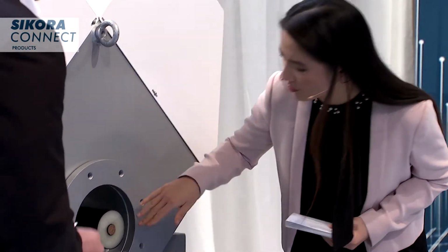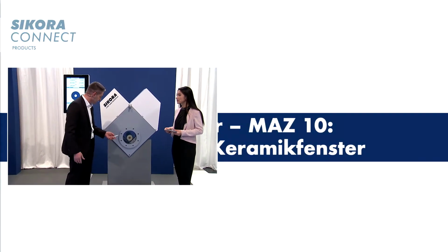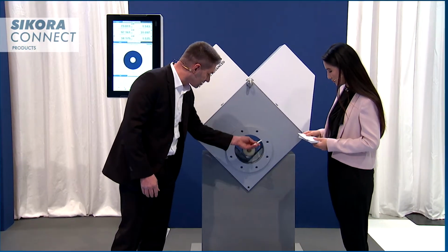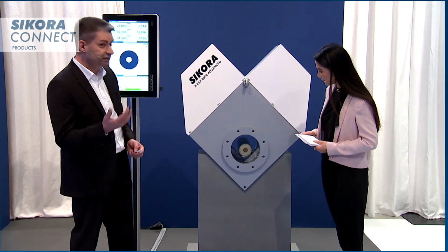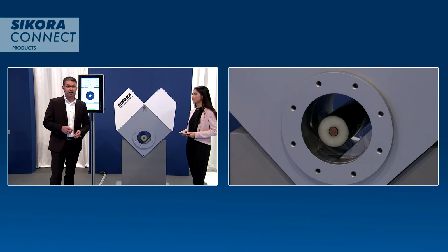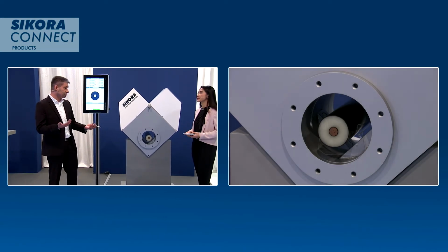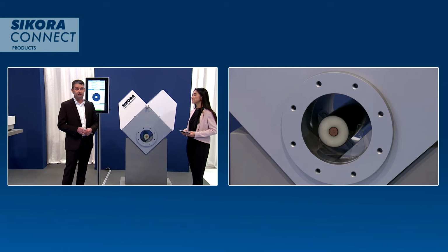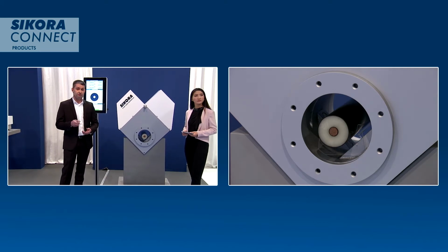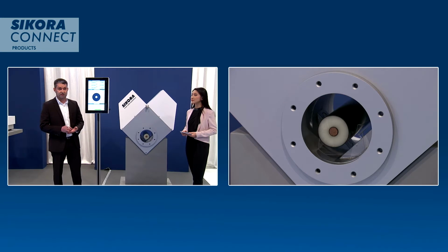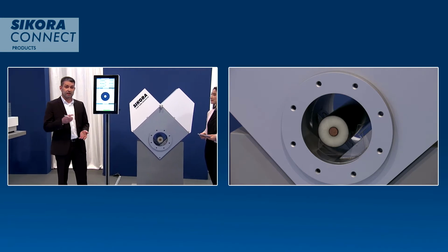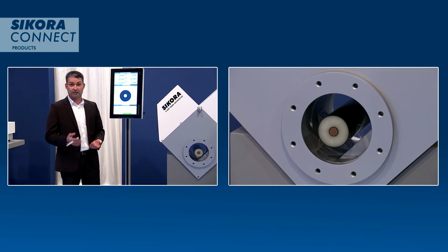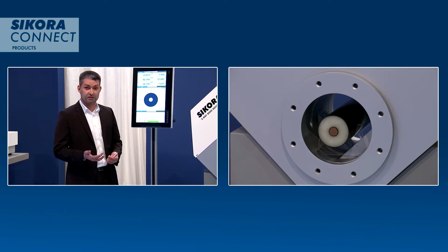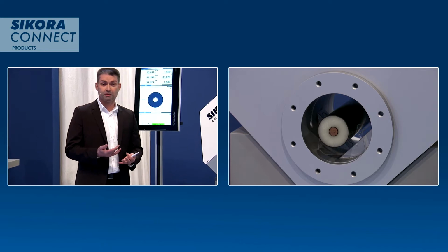If I look inside, there seems to be a window. Yes, we have 4 windows in total, because the X-ray beams need to go through the cable somehow. On the lower side, you have ceramic windows. In the past, we had beryllium windows, which is a heavy metal and not so ideal for the environment. But back in 2007, we made a big step in optimizing the device and exchanged the beryllium windows for ceramic windows. The great aspect of ceramic windows is they're not toxic, but they also have an inbuilt lotus effect, like a real plant, so dirt rinses off automatically.